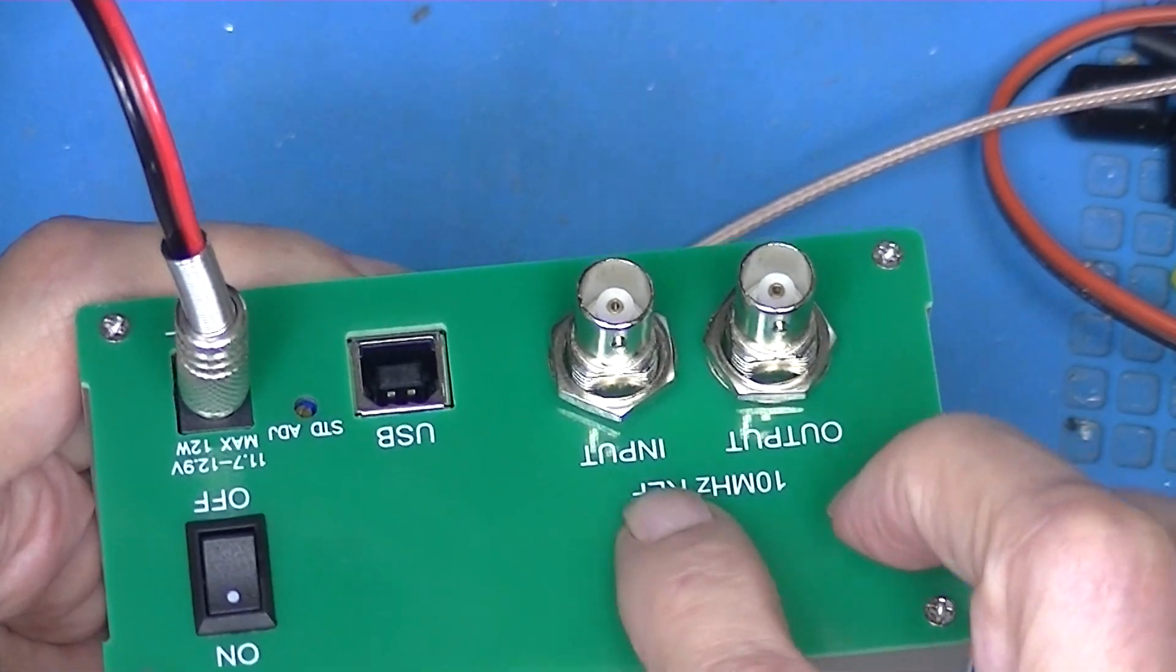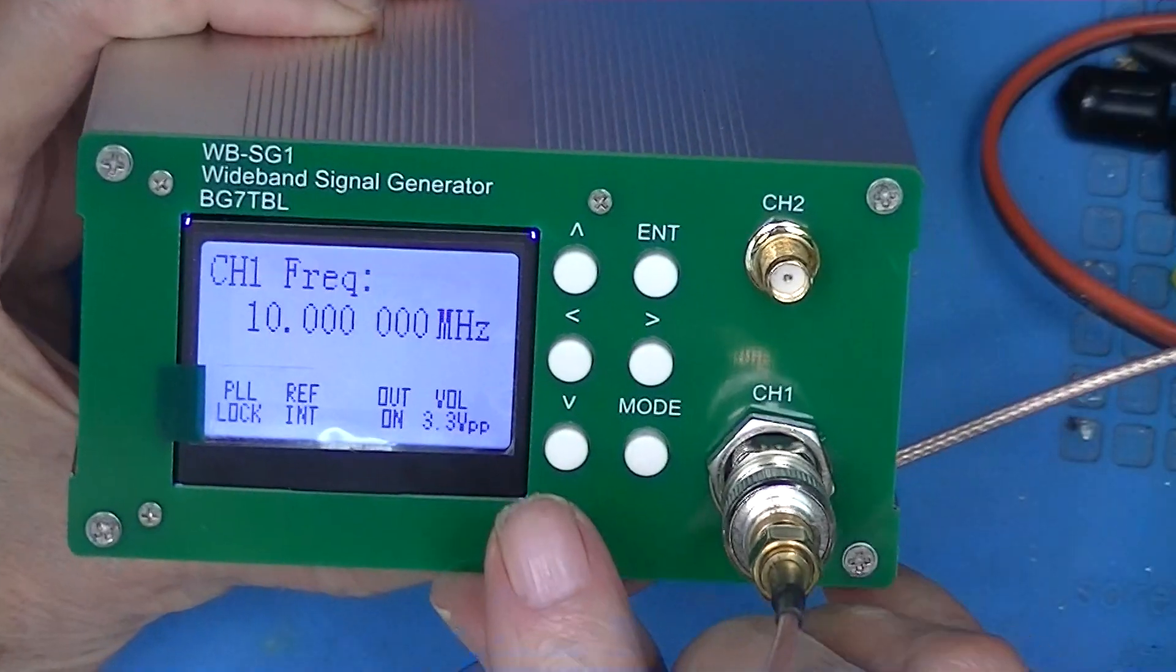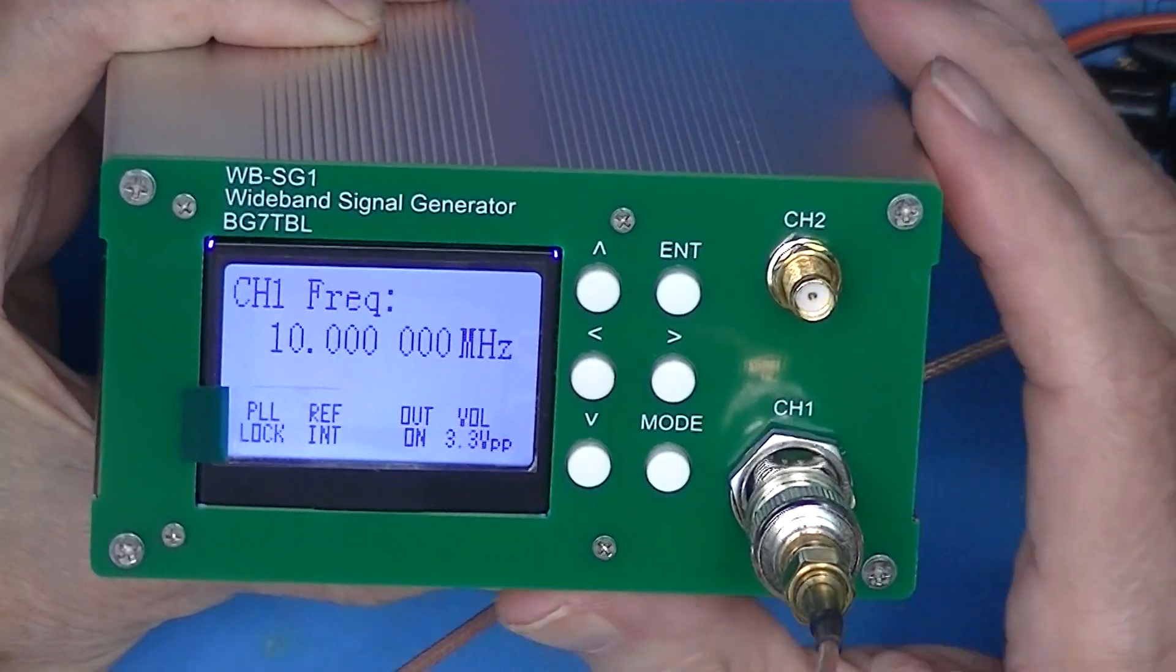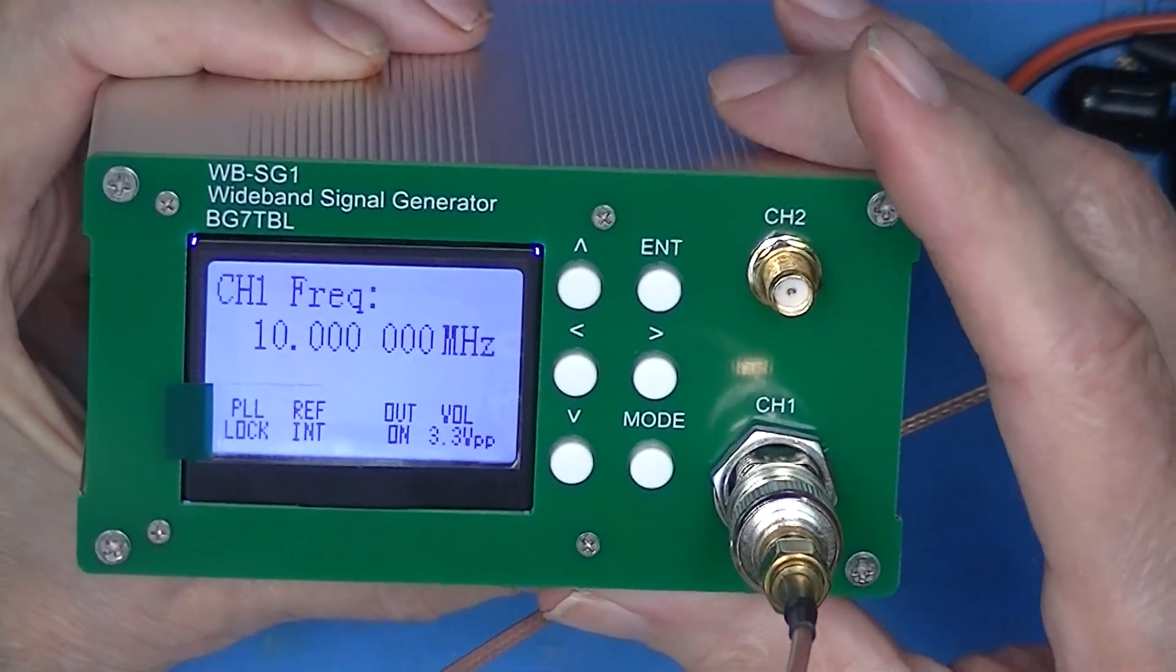This thing accepts or will accept an external 10 megahertz input, 3.3 volt peak-to-peak, as indicated on the generator.